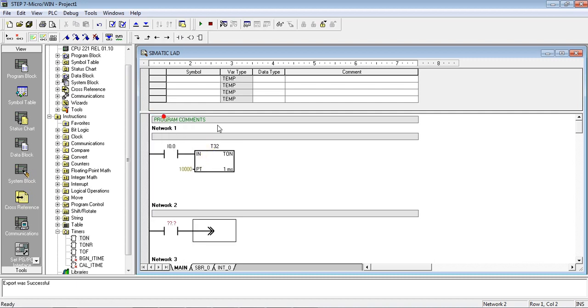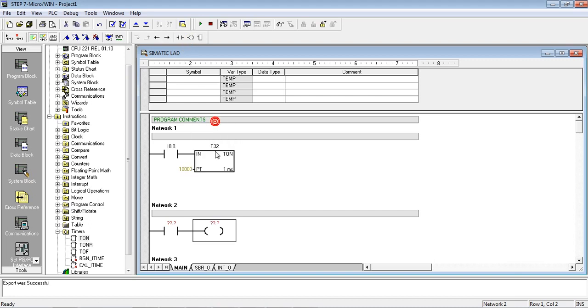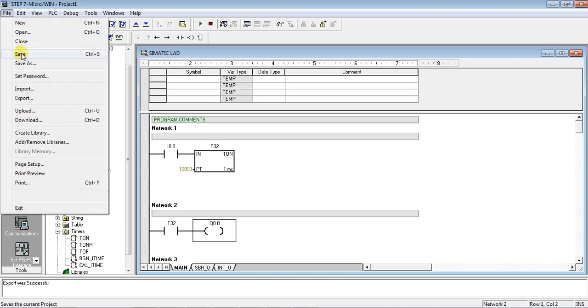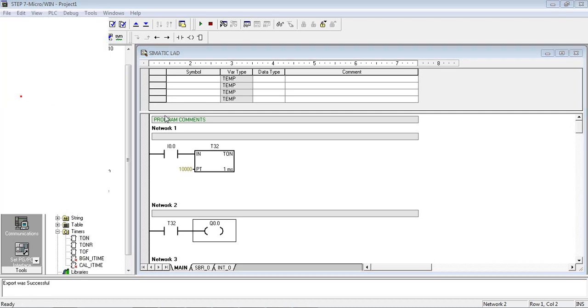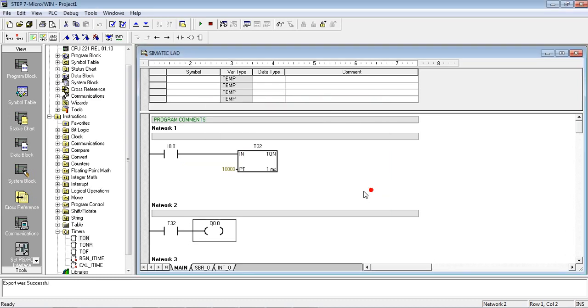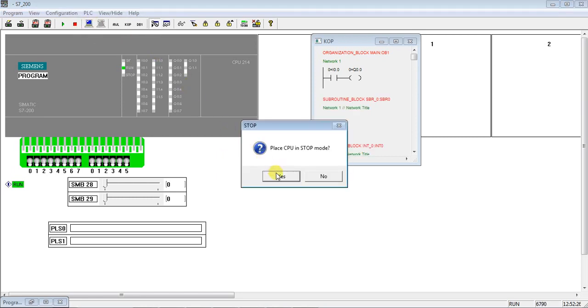So we are using TON timer, so addressing T32. So preset time we have given 10,000, so this is for 10 second delay. Okay, so this is output of timer T32, and we connect it to output device Q0.0. So again you export this program, so P2 is the file name that we had exported.